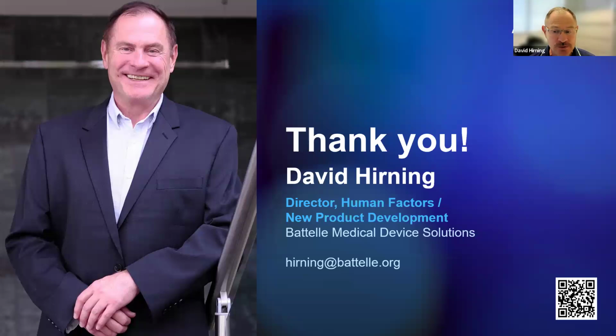I would propose that the methodology is built upon 21 CFR 860, and others, but the main ones that we presented in the slides here: 21 CFR 860, IEC 62366, as well as various FDA guidances that are published. The guidances are interpretation of relevant CFRs.